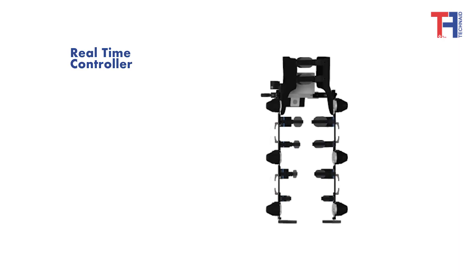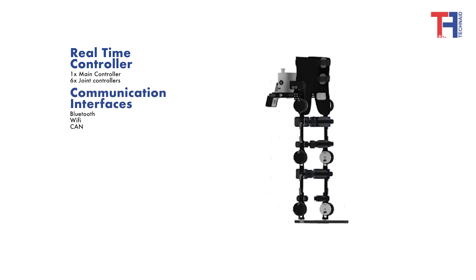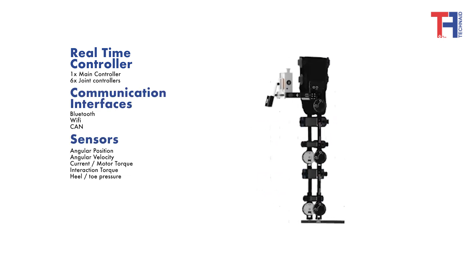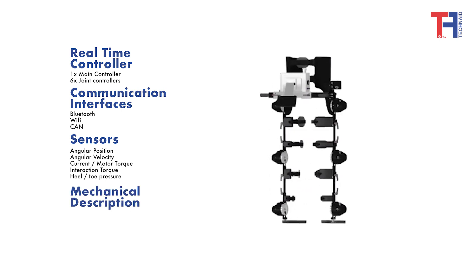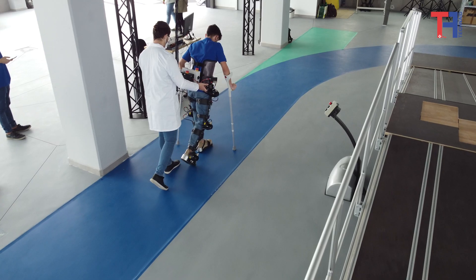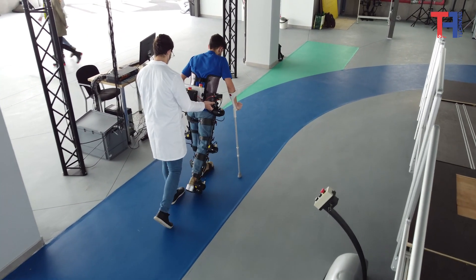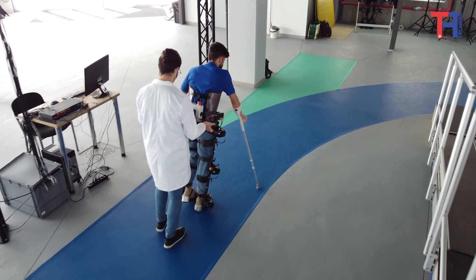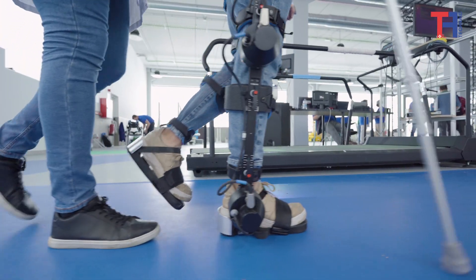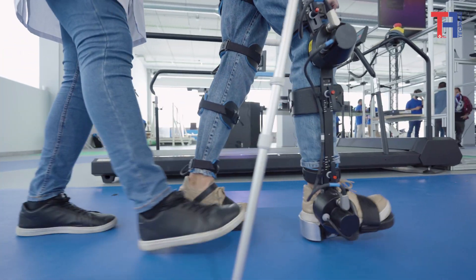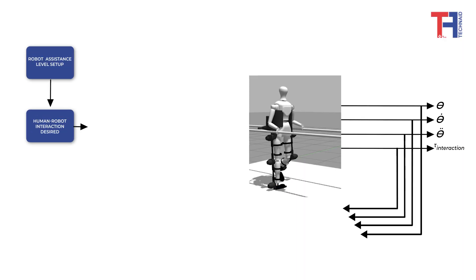It has six lower limb joints actuated in the sagittal plane. It also features several sensors that allow real-time measurement of data, such as the interaction of the device with the human, the speed and exact position of each movement, and the moment of pressure on the ground during the step. With the feedback of this data, the exoskeleton can modify the movement assistance and adapt it according to the wearer's needs.